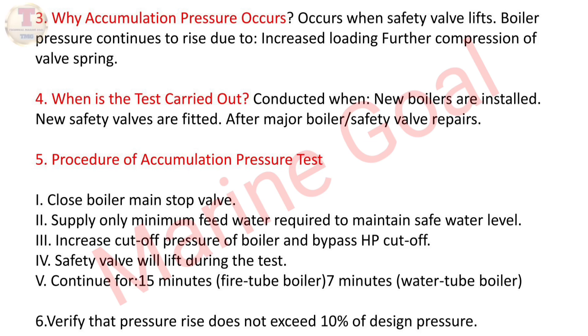When is the test carried out? It is conducted when new boilers are installed, when new safety valves are fitted, or after major boiler or safety valve repairs. Procedure: step one — close the boiler main stop valve.